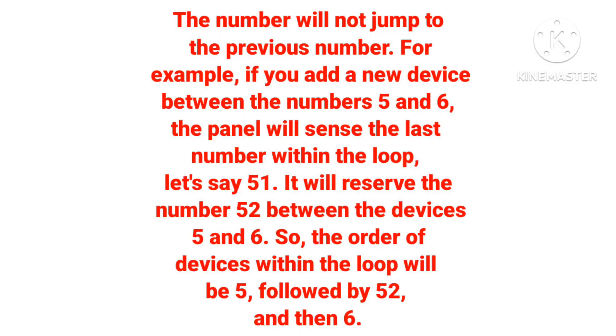But with safe addressing, the panel will give its unique address. If you add any device between five and six, the panel will give it the last address. For example, if we have 51 as the last device, the panel will give it address 52. So the location will remain 1, 2, 3, 4, 5 — then 52 — then 6. That is the benefit of safe addressing.